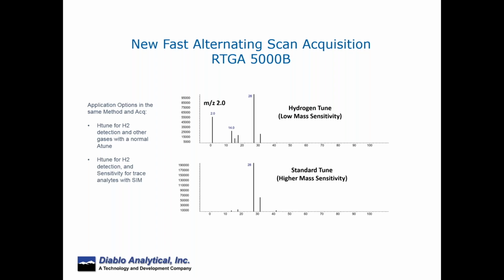In the example shown here, the first acquisition would be set up with a hydrogen tune capability. That hydrogen tune allows you to see down to mass 2.0, also to see helium, lower mass components. And then the second acquisition would be a standard tune for looking at all the components up to high mass. This mass spec goes up to very high mass, very much higher than you would typically go for most gases. And so we're able, within a single method, to get both types of acquisitions in a single run.